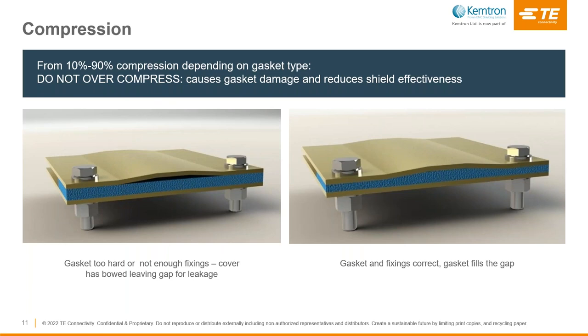To get good contact between the gasket and the enclosure, a certain amount of compression needs to be applied, varying depending on gasket type and application. The assembly design needs to be sufficiently rigid with sufficient bolt spacing to ensure that the gasket is compressed along its entire length. If this is not considered, bowing between the fixing locations may occur, which will reduce the shielding performance of the gasket.